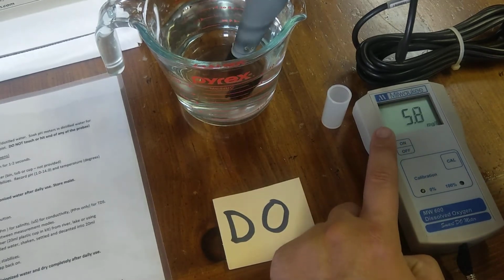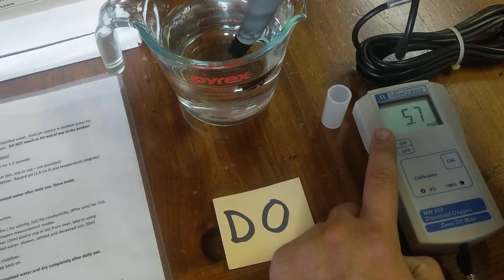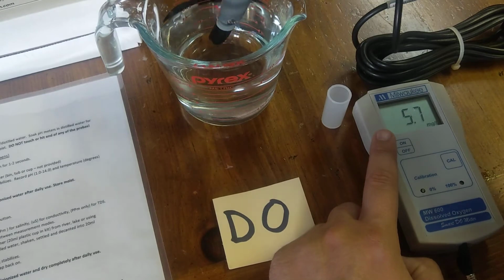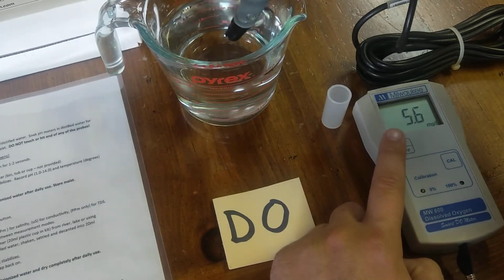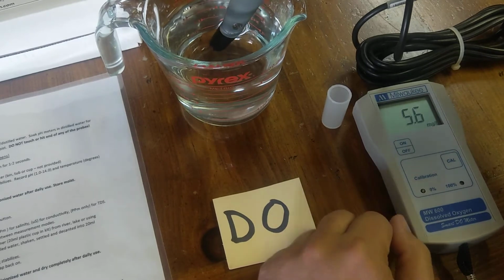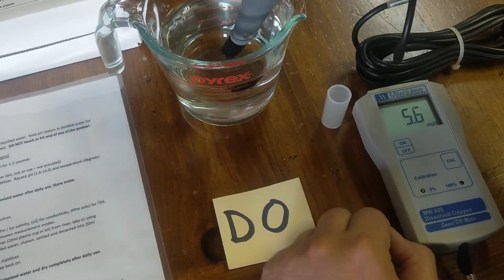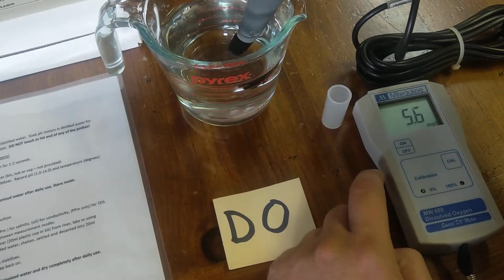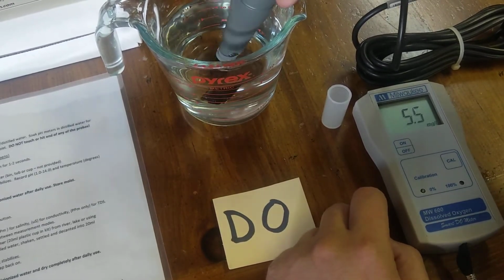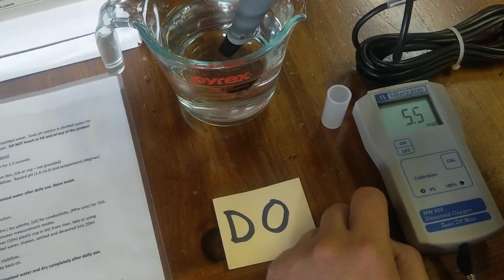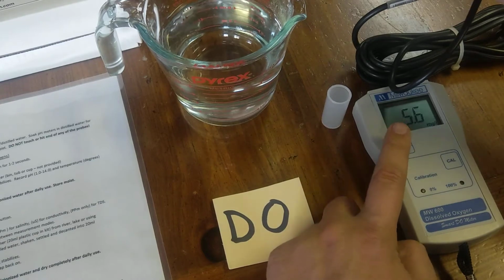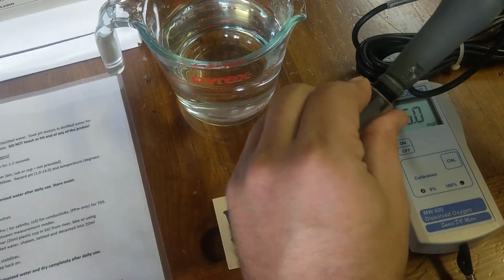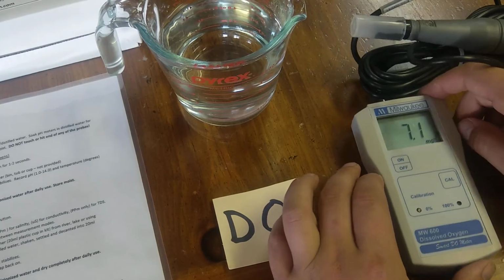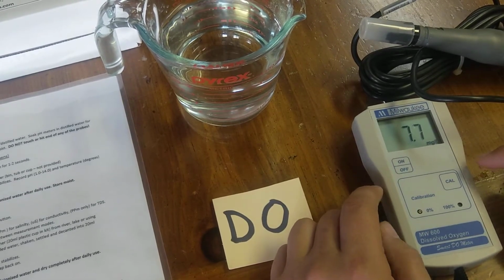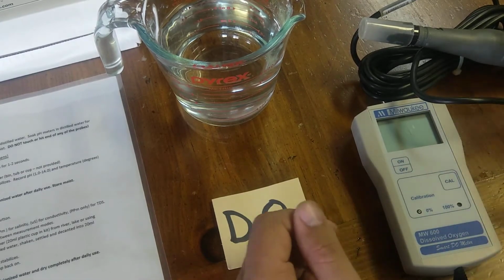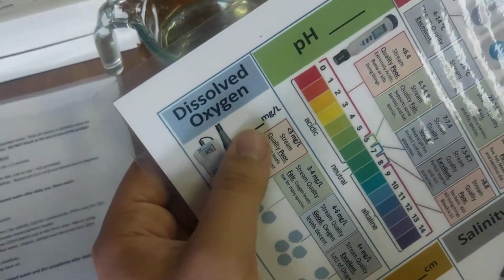So after it stops moving, you'll notice it's at 5.7 here, not bad. That is the reading, 5.6. That is the reading I'll usually take, after, let's say, 10 seconds or more of being the same value and not moving, I'll use that value here. So, 5.5 it looks like for our reading. Alright, it went back up to 5.6, so that's good. So 5.5, 5.6. I would say 5.5 would be the reading, and then you can shut it off. And there we go. At that point, students can record their value on here.